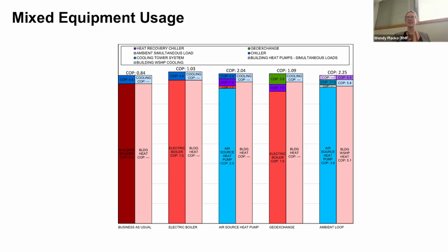I love this idea that if simultaneous is an option, since that's the highest COP, we want to be running that as much as we can, and then we start switching. So the idea of geo-exchange, we run simultaneous as much as possible, then switch to geo, which is slightly less COP, for part of a shoulder season. Then in another season where we're in core heating and cooling mode, we might go to air source heat pump next, depending on the weather. Trying to line up these systems to be active when they're most efficient is a really interesting concept that you all plan so well. That's why we look at things on an hourly basis.